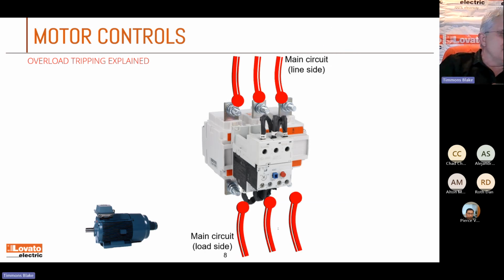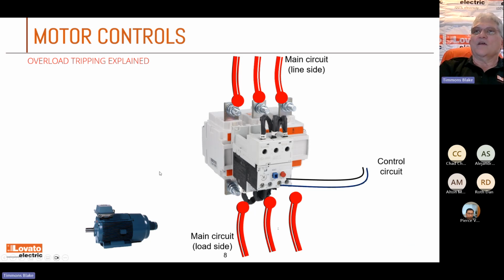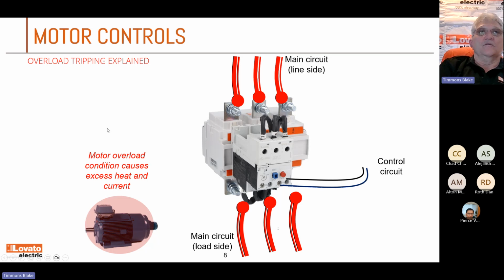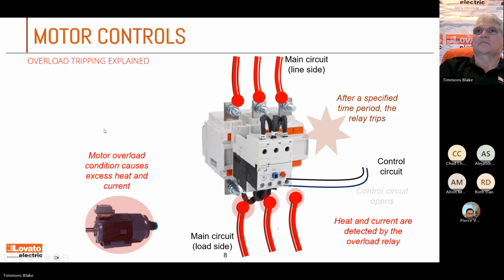Here's my animation on the overload tripping. Okay, so you have your motor, your line side coming in from the contactor, and you're feeding out to the motor. Okay, you have that control circuit that'll go up to the coil on the contactor. All right, you have a motor overload. Excess heat happens, right? Heat and current are detected by the overload. Boom, little arc. Yeah, that's when we turn it off.